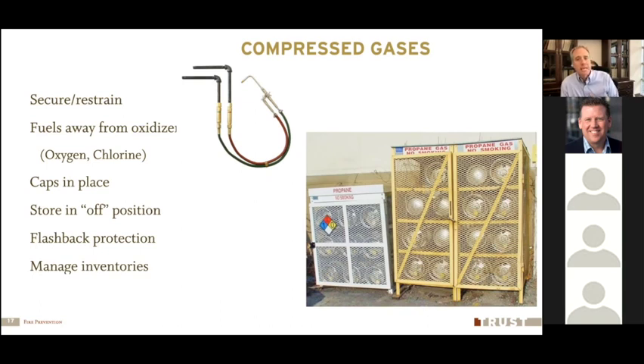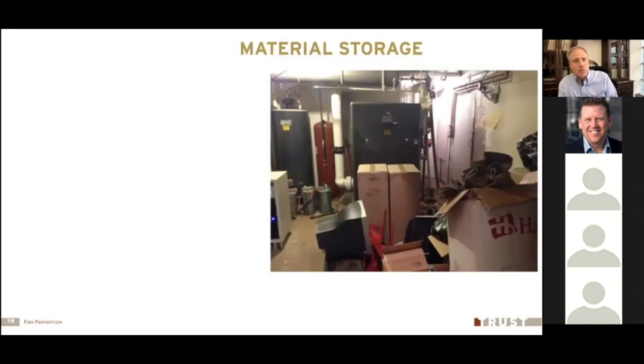Make sure that those containers are secured in place. They're very heavy. If they tip over, the fall could damage the valves and cause a release of those gases. And they could even cause a serious injury to a person if they should fall onto somebody's leg or foot. And so always make sure that we have good containment and security for our compressed gas storage. Keep the caps on top of the valves on your gas cylinders. Make sure that the valves are in the closed or off position. Make sure when you're using that equipment that you're using flashback protection. And again, manage your inventories. Make sure we're not storing more flammable gases or materials in the facility than is really necessary.